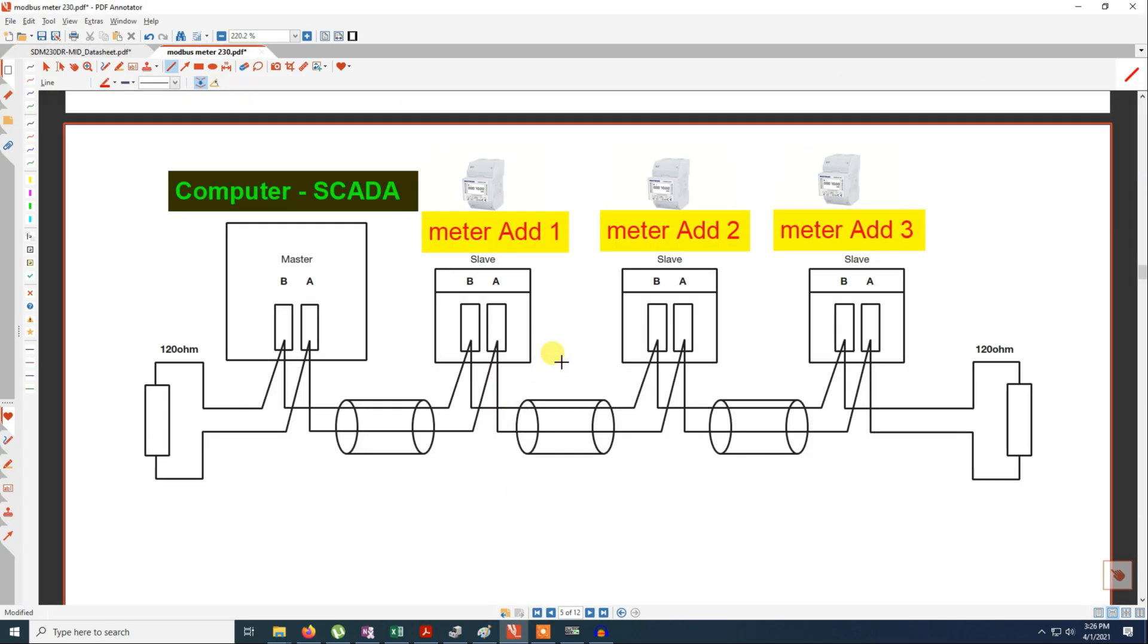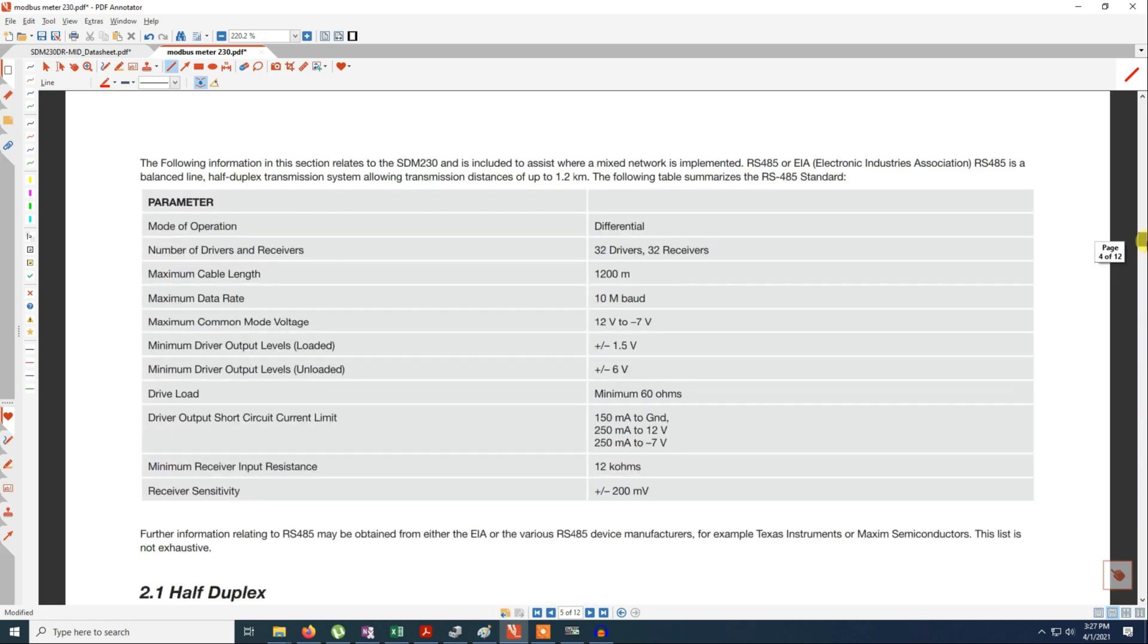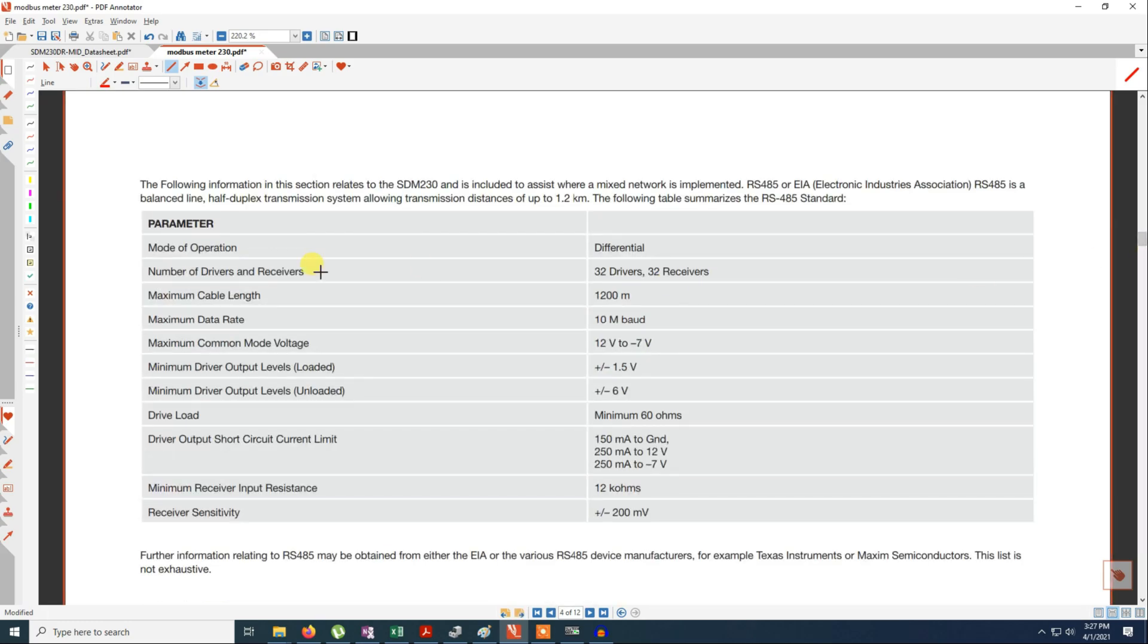So how to wire it if you have multiple meters? You just give address to the different meters - address 1, 2 and 3. Then you connect the wires in parallel. That is B with B, A with A. And you continue the loop. And so this is the limitation of the RS485 device, that is 32 devices up to 1200 meters.